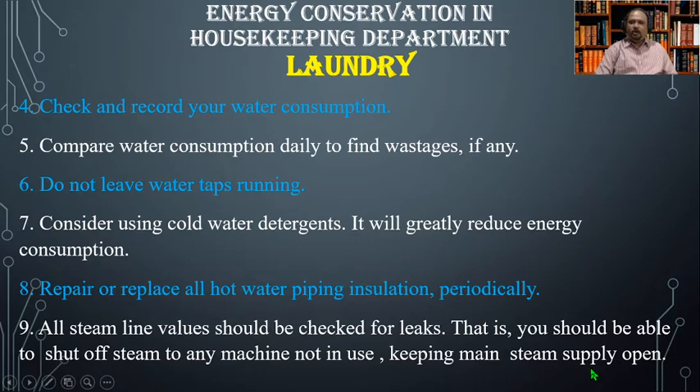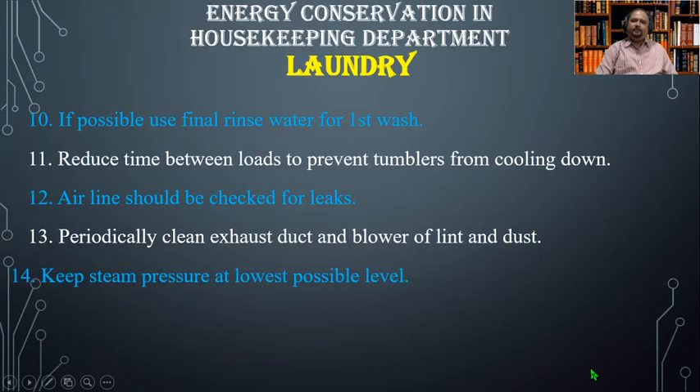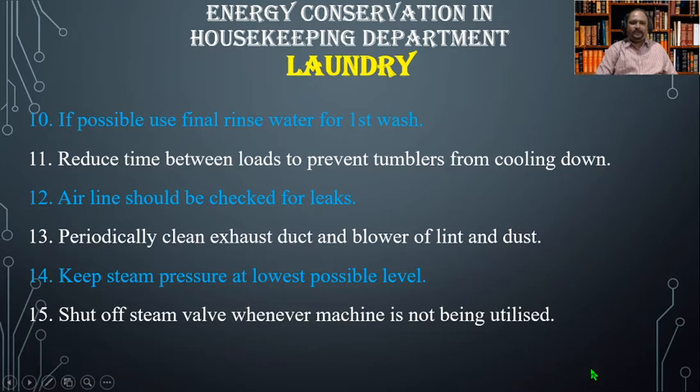Number six, do not leave water taps running. Number seven, consider using cold water detergents — it will greatly reduce energy consumption. Number eight, repair or replace all hot water piping insulation periodically. Number nine, all steam line valves should be checked for leakage; you should be able to shut off steam to any machine not in use, keeping main steam supply open. Number ten, if possible, use final rinse water for the first wash.